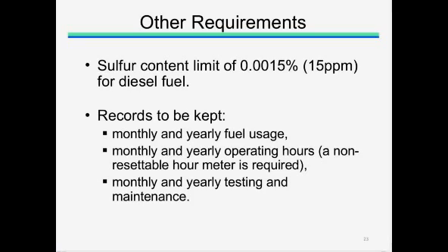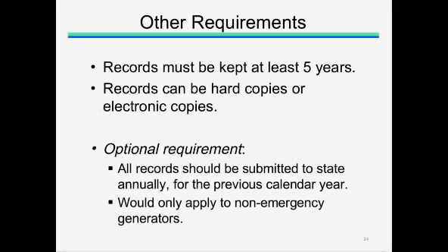Additionally, a non-resettable hour meter is required to be installed on a stationary generator, which makes it very easy to determine the monthly operating hours. Most, if not all, new generators include a non-resettable hour meter installed by the manufacturer. The model rule also requires all records to be kept for 5 years, and they can be kept as either hard copies or electronic. The model rule also includes an optional requirement which a state may choose to adopt if it wishes. This optional record-keeping requirement would require all non-emergency generators to submit all of their records for a calendar year to the state at the end of each year.